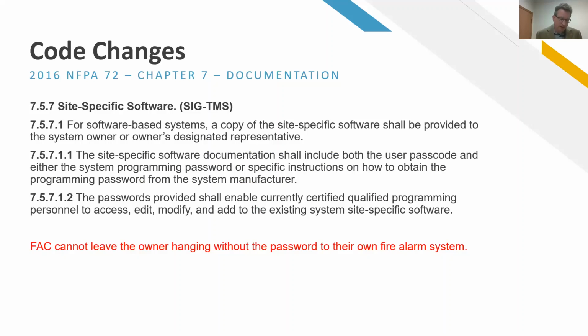This is language that says the fire alarm contractor is responsible for providing those passwords, or instructions on how to obtain them. So if you're having trouble with the fire alarm contractor not playing nice, you have some leverage, because it's in the code, which is a legally binding document adopted by the state. And you can get the fire marshal involved too if you have to.